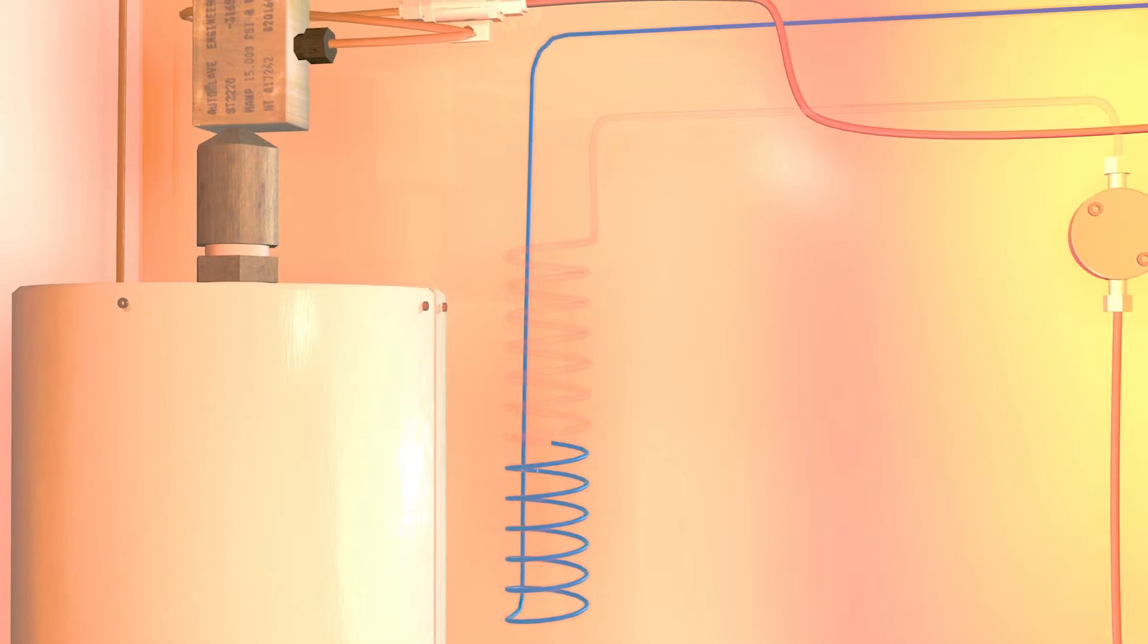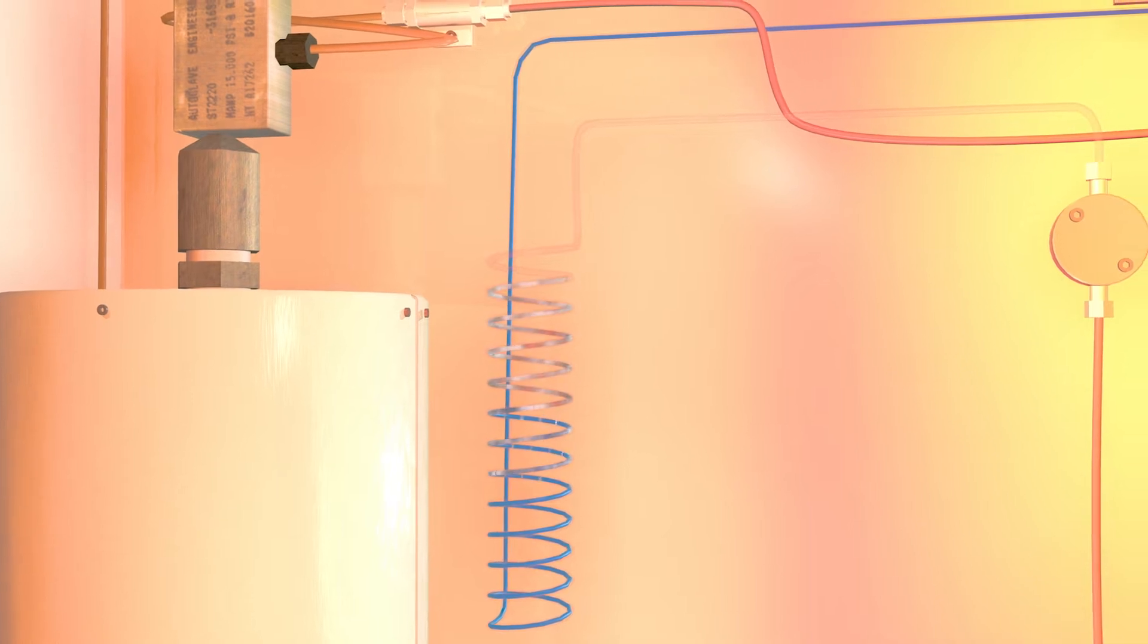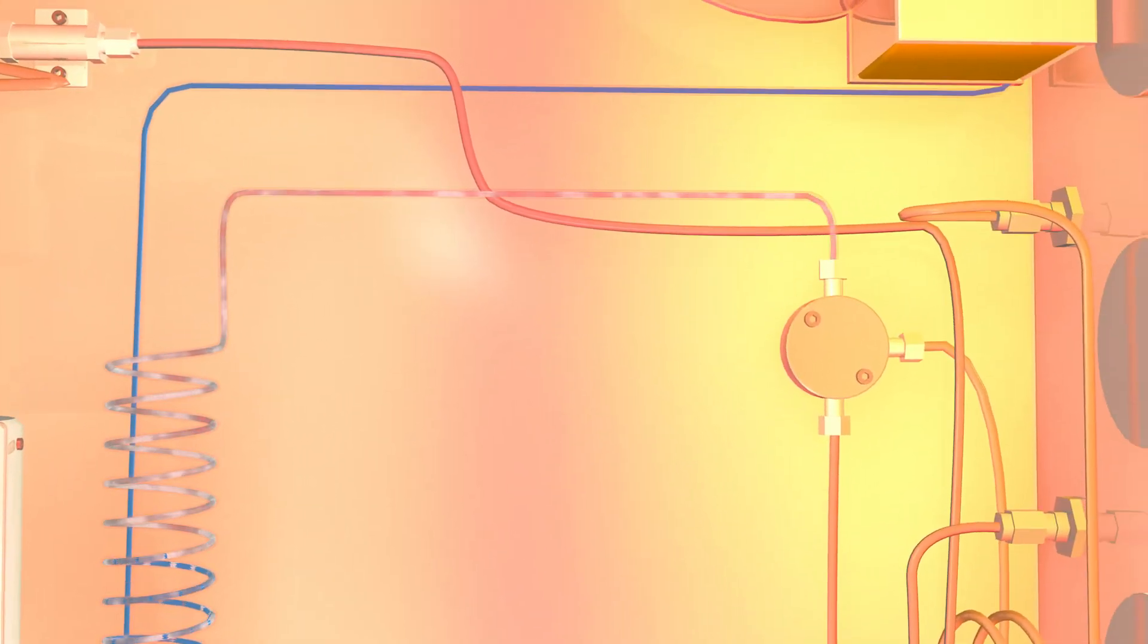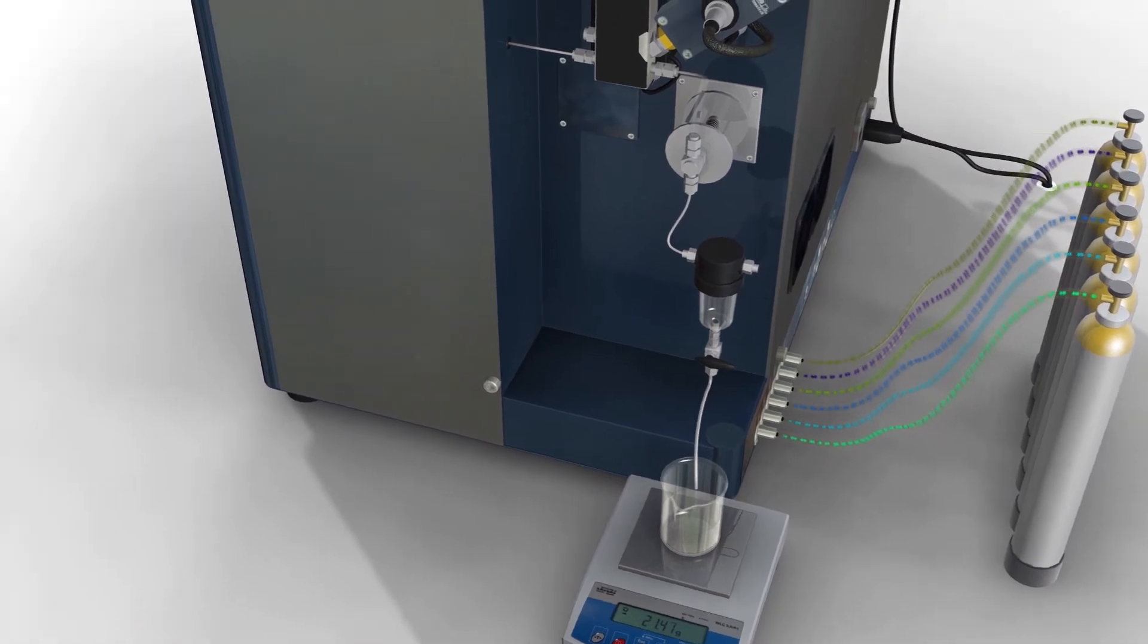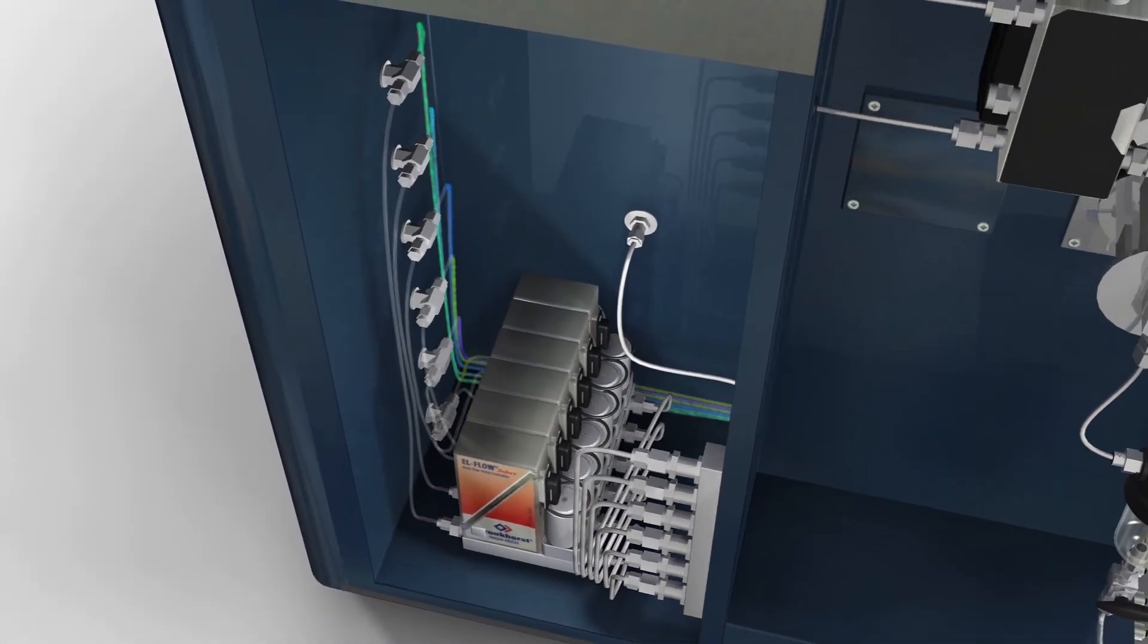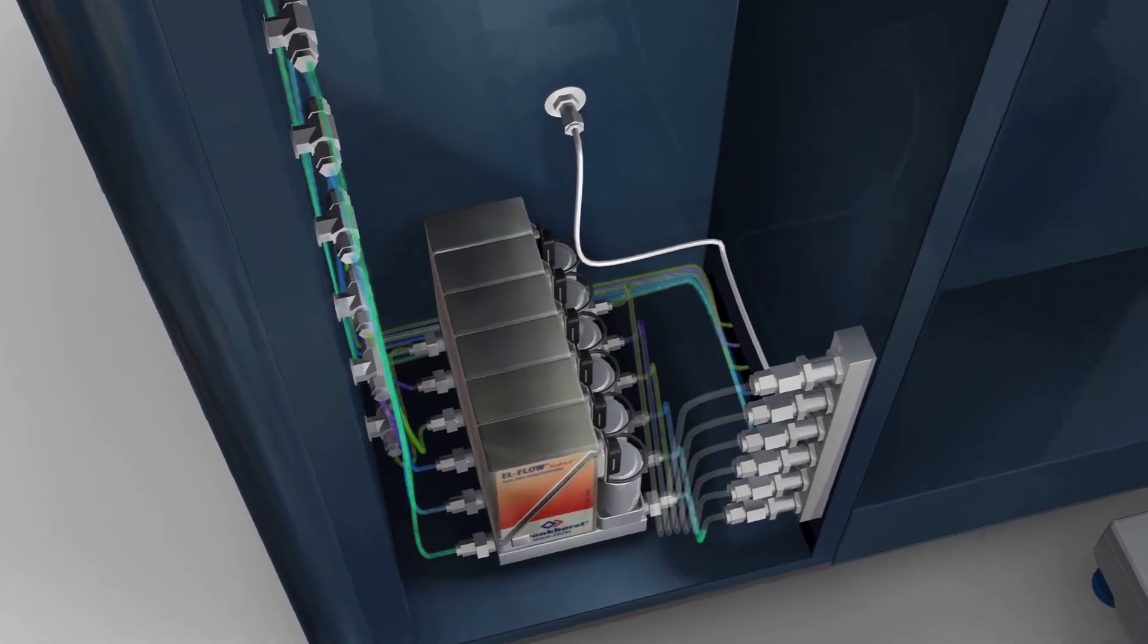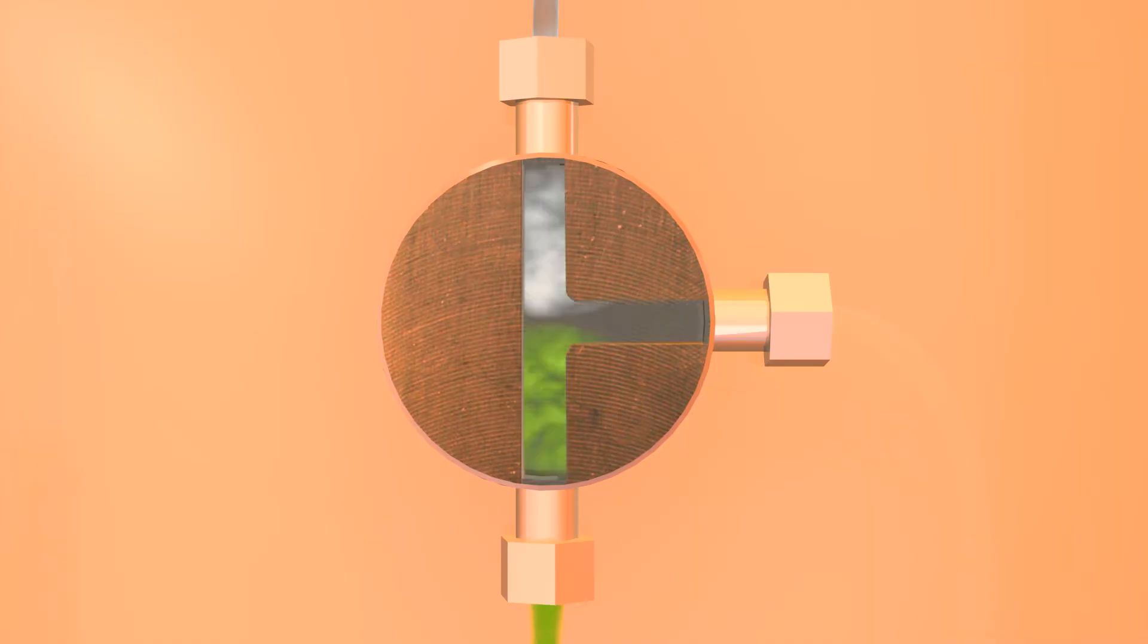The liquid is vaporized as it passes through a proprietary heated evaporator. A series of mass flow controllers are used to feed gas reactants into the heat exchange zone to bring them to the same temperature as the vapor. The gas and vapor are blended in the mixer.